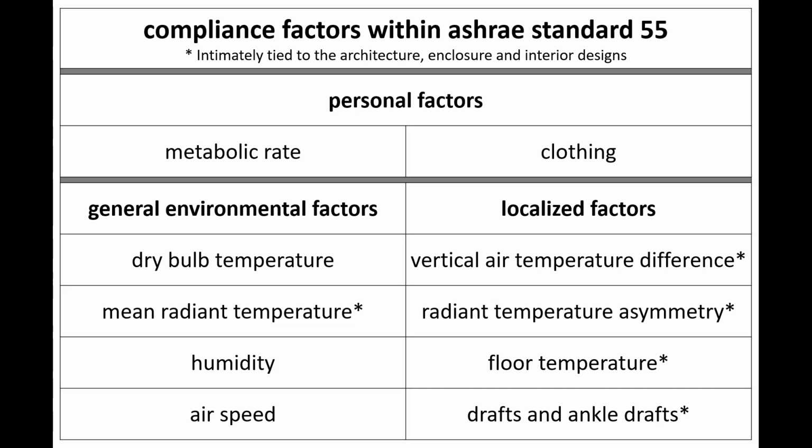This is in fact what people sense is the operative temperature, not dry bulb, not mean radiant, but the two of them together. So where the person goes, so goes the operative temperature. And because operative temperature includes MRT, where the person goes, so goes the MRT. And so this is what's really important.